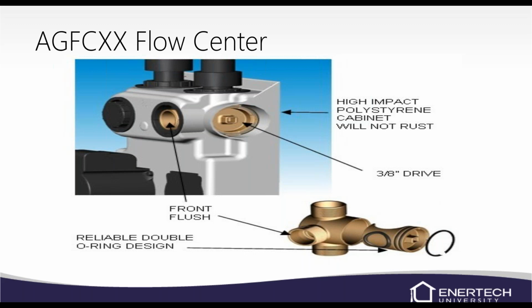Make sure you just take the snap ring off and then you'll put your 3/8 drive into that square hole and move it back and forth, while you're pulling out a little bit, and that whole piece will come out and it'll be those 3 gaskets, and you can replace just those 3 gaskets. And then when you're putting it back in, it will come with some grease. You can put that grease on there, and that insert will go in a lot easier. It's not a real easy thing to get out because it's real tight. Obviously, there's a real fine clearance. So it's a little bit difficult to get out, but it definitely can be done. I've done it.